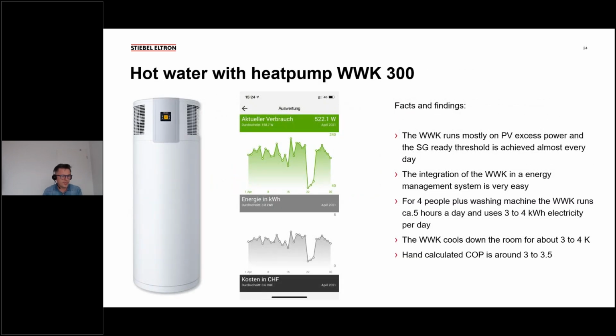Hot water with the domestic hot water heat pumps. In this case, I use around about 3 to 4 kilowatt hours a day for hot water, for 4 people plus the washing machine, which I also connected to the hot water tank. The heat pump cools down the room by 3 to 4 Kelvin when it's operating. I'm not measuring flow and energy on hot water directly, but the controller has an indicator of how much energy is in the tank, so I have a hand-calculated COP value, and it's between 3 and 3.5.